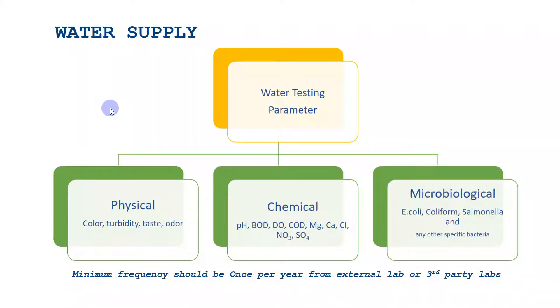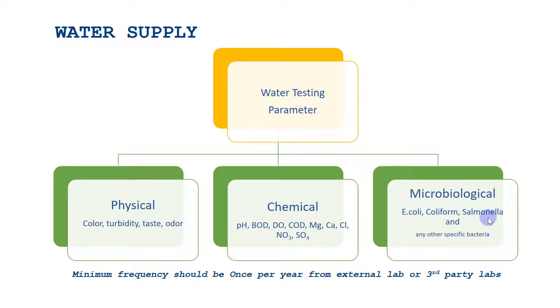For water supply, you need to have testing of the water. The parameters to consider while testing from external laboratories are: physical parameters — color, turbidity, taste, and odor; chemical parameters — pH, BOD, DO, COD, magnesium, calcium, chlorine, nitrate, and sulfate; and microbiological parameters — minimum E. coli, coliform, and salmonella must be included, plus other specific bacteria required according to your product. Remember, even if you do in-house lab testing, you are still required to have a minimum of one third-party lab test per year.